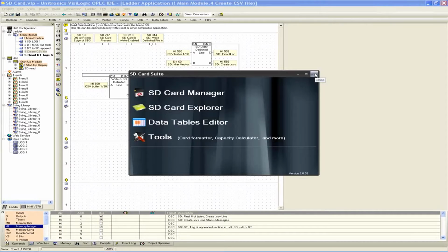The original method is from information mode. I can't show you that on remote access. Information mode isn't supported in online test mode here, but I can tell you, if you go into information mode, you enter your default password on your PLC. To get into information mode, you hold down the touchscreen for 4 seconds. It'll ask you for a password. The default is 1111.